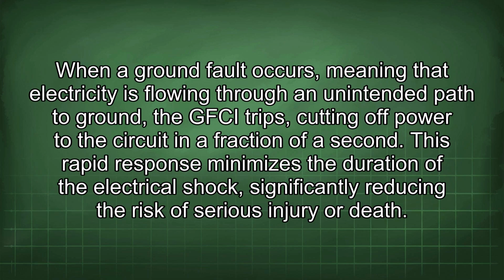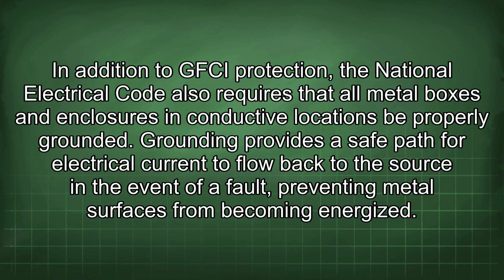When a ground fault occurs, meaning that electricity is flowing through an unintended path to ground, the GFCI trips, cutting off power to the circuit in a fraction of a second. This rapid response minimizes the duration of the electrical shock, significantly reducing the risk of serious injury or death. In addition to GFCI protection, the National Electrical Code also requires that all metal boxes and enclosures in conductive locations be properly grounded. Grounding provides a safe path for electrical current to flow back to the source in the event of a fault, preventing metal surfaces from becoming energized.